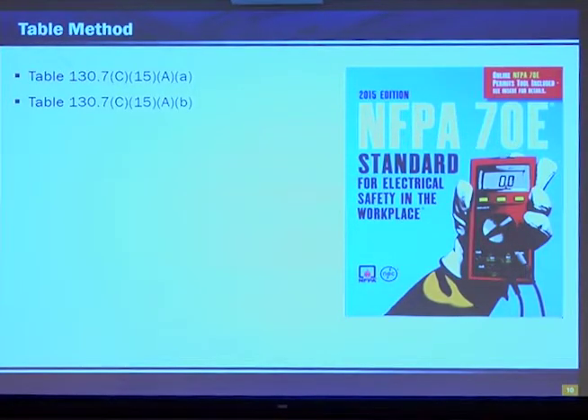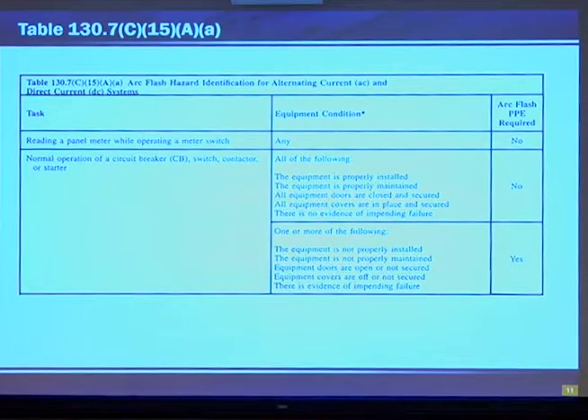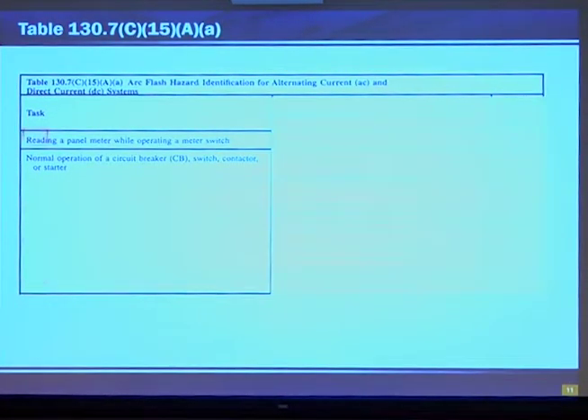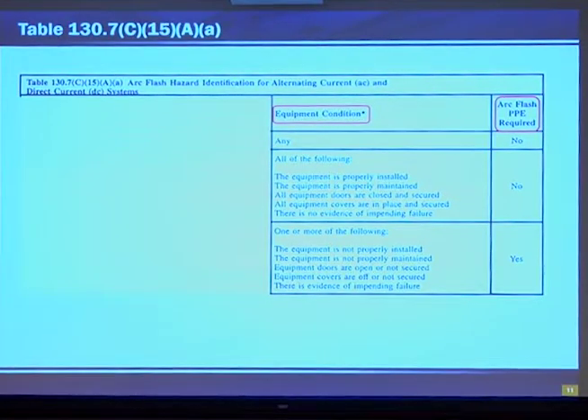Let's start off by using the table method. Table 130.7(C)(15)(A)(a) and Table 130.7(C)(15)(A)(b). Mouthful, isn't it? Let's call them Table A and Table B for short. It'll be easier on all of us, I promise. So these tables will first decide, is PPE required? And if it is required, what level will be needed? And also the ArcFlash boundary that we would need to work in a safe environment. Table A. On the left-hand side of the table will be the task that we are performing. On the right-hand side of the table will be the equipment condition and the ArcFlash PPE needed for that task at hand.